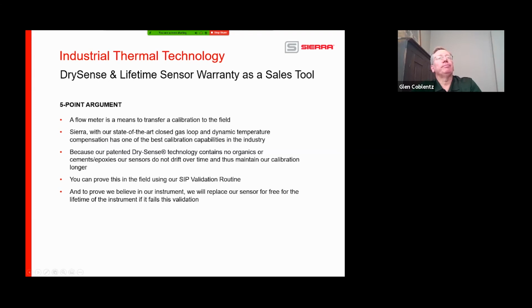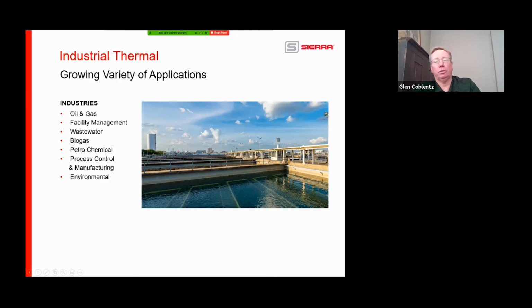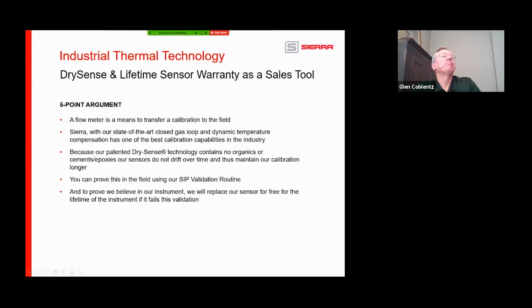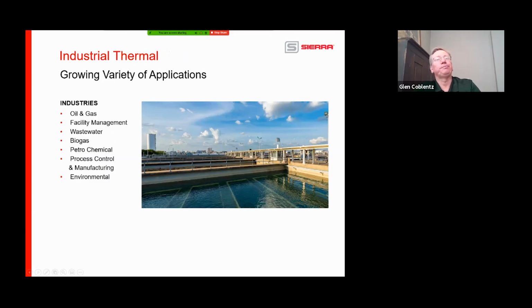Here's a good 5-point argument that you can use when you get into this discussion. A flow meter is a means to transfer calibration to the field. We talk about our flow loop, DrySense technology, no organics or epoxies. It's going to be very, very stable over a long period of time. You can prove this by using the validation routine in the SIP. And again, we'll replace the sensor for free and for a lifetime in the instrument if it fails this validation. So again, as said before, we've had a lot of them damaged, but none of them have actually had a sensor fail. So very, very powerful.